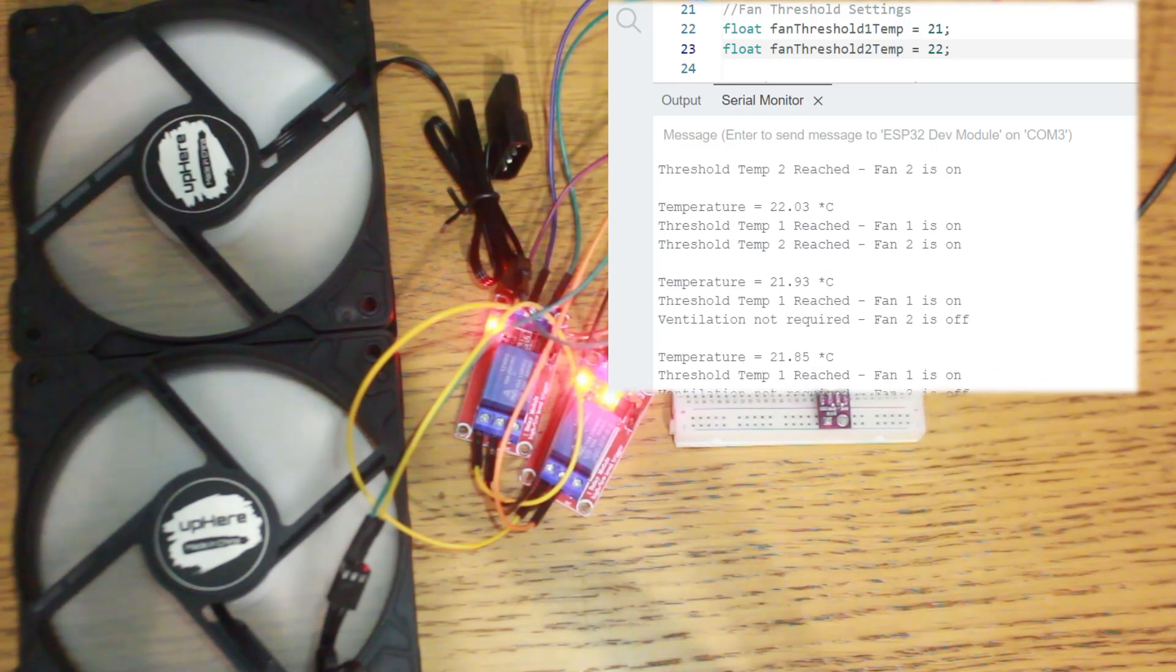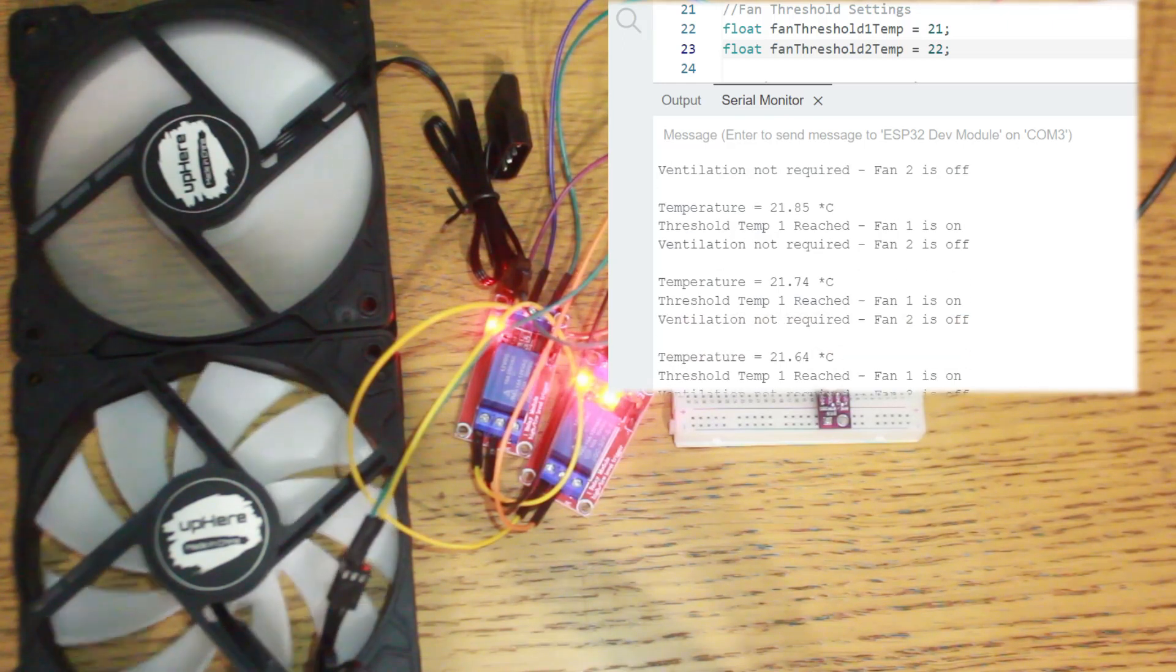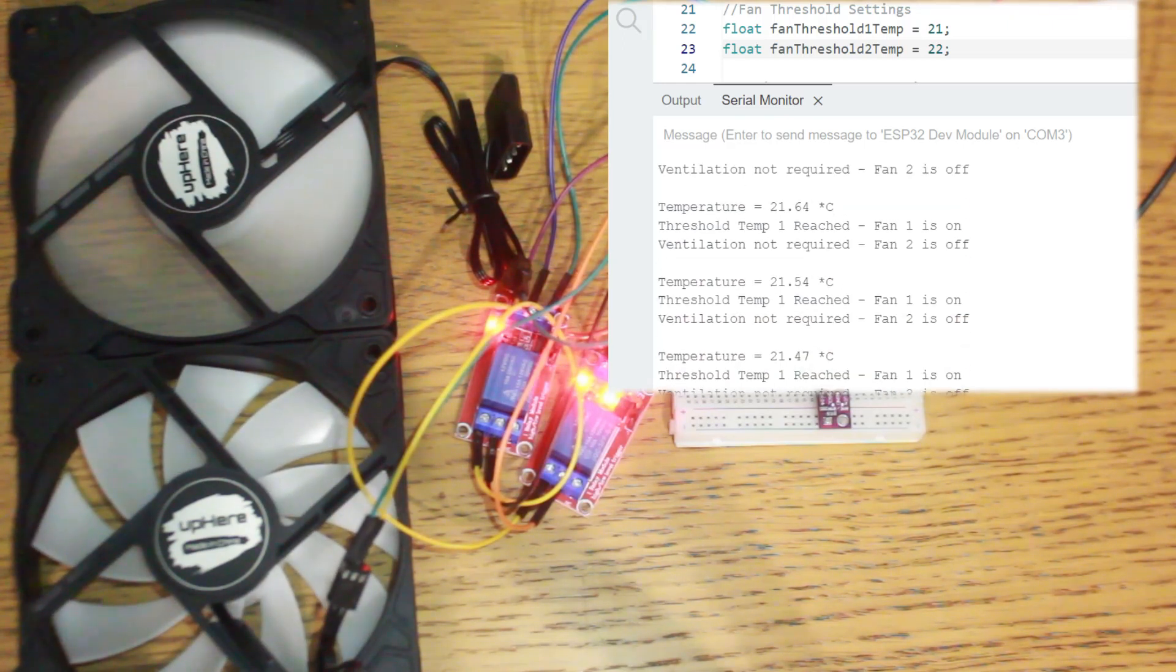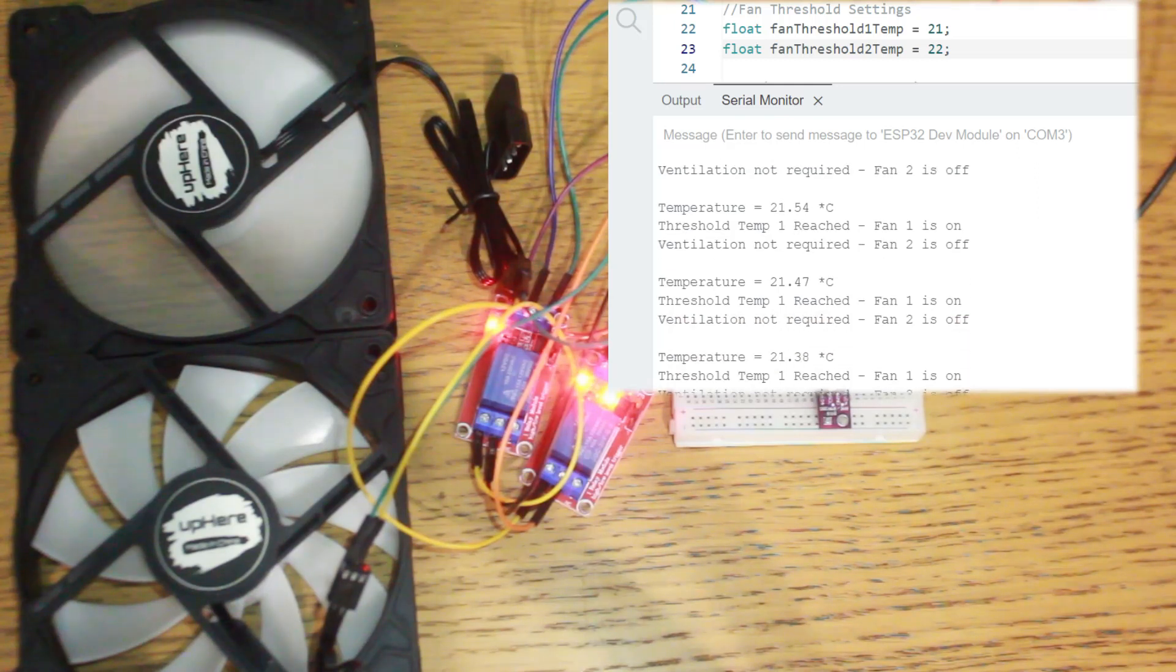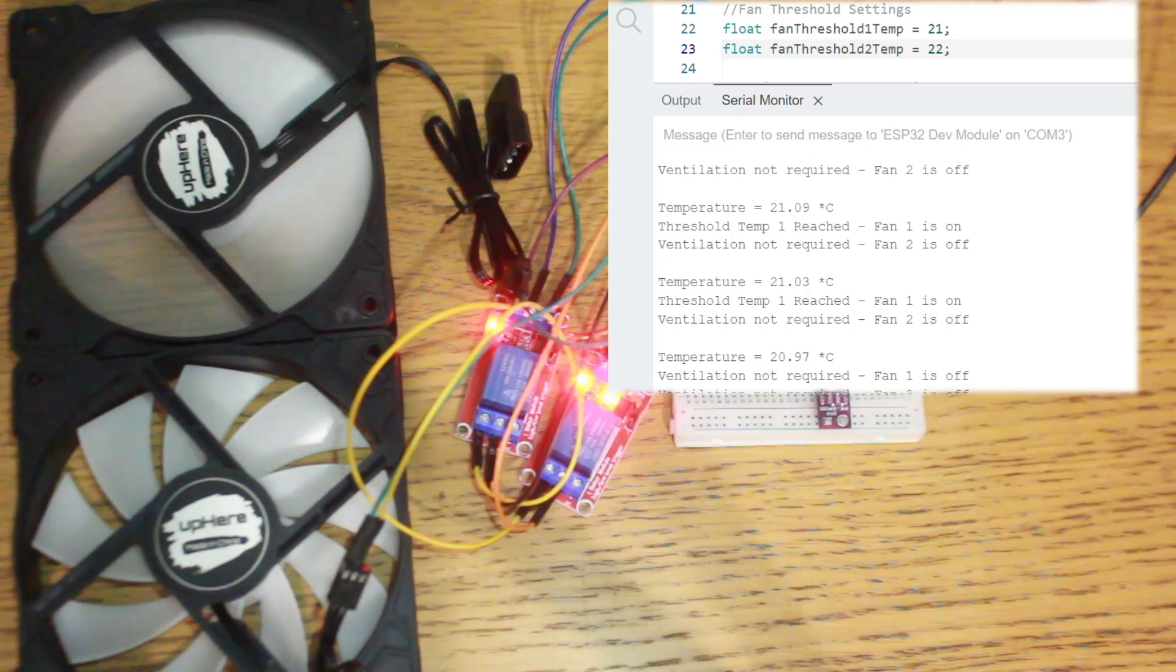The second fan is switched off as it comes below the second threshold and then eventually it will continue to go down until it comes under the first threshold where the signal will be sent to the relay to turn it off again. Yep, there we go.